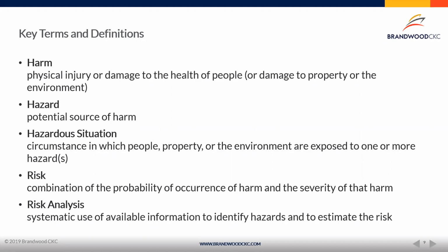So if we have things that are going to potentially cause hospitalization or have a potential impact of death to the end user, that's obviously much more severe than somebody having a negative reaction to the usability, or a small distaste for the device. That's not the same type of severity that we're looking at. So we have to grade those things, and that's where we come up with the difference between severity.